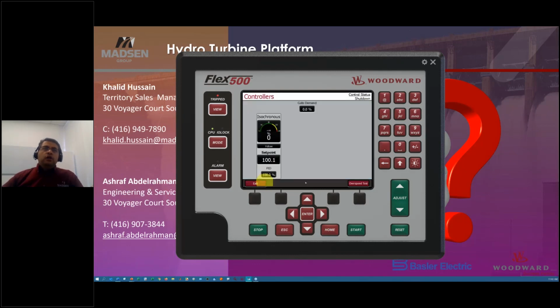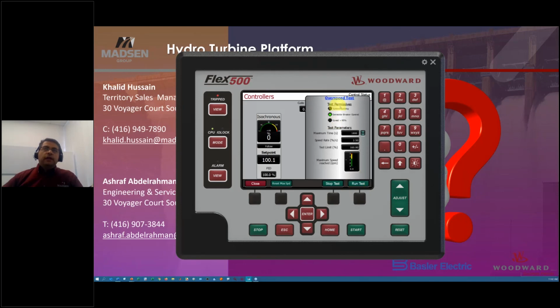So as you can see here, you can do an overspeed test. If the user would like to do an overspeed test, to test how the unit will behave during overspeed, yes, you can run that test through the unit itself in a very safe manner, because it will not reach above 120% or above a certain value. So we have a test limit for the unit itself. If the test limit is configured to be, here it is 160, maybe you can put it at 120%. So you run the test, you start your turbine, and you know that it should be tripping at 110% of the rated speed, or 120%, or even 140% of the rated speed.